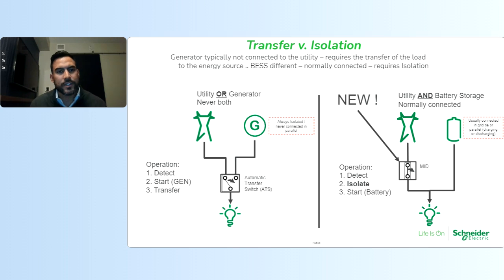So we like to show this slide here to distinguish the two differences between a transfer switch and an automatic interconnection switch. If we look at the left side, a generator is typically not connected to the utility. It requires the transfer of a load to an energy source. And what we mean by that is when the transfer switch loses power, it will remain connected to source one. And then once it senses that source two power is available, i.e. the generator here, it would transfer over to source two.